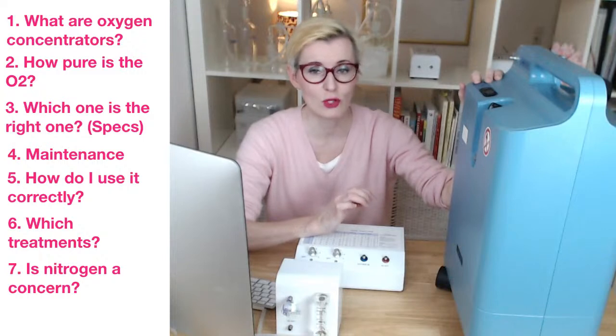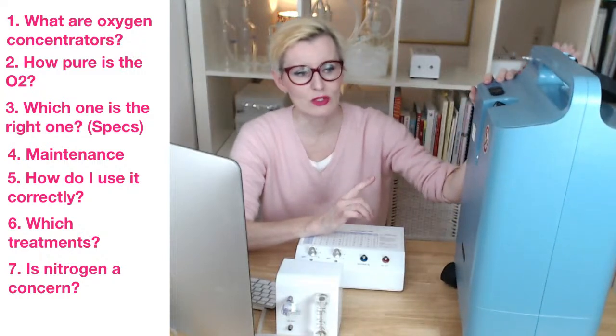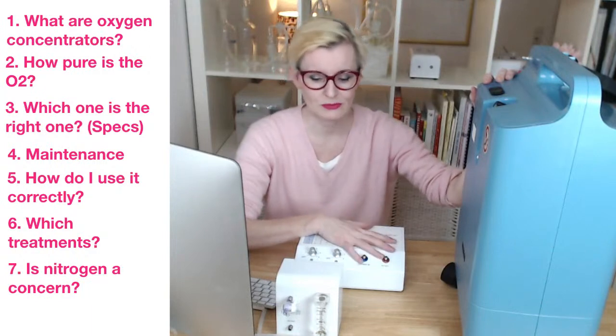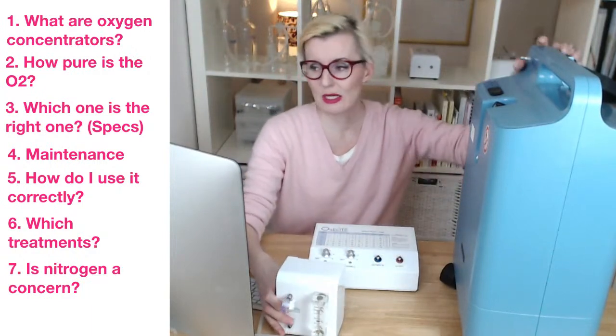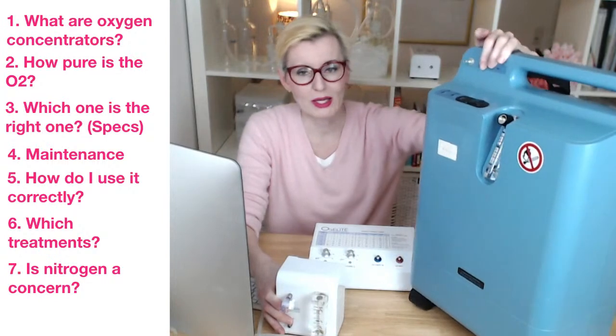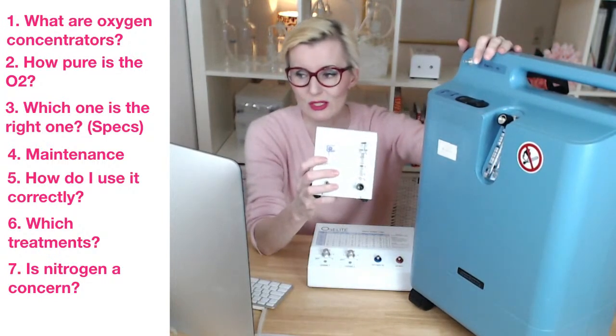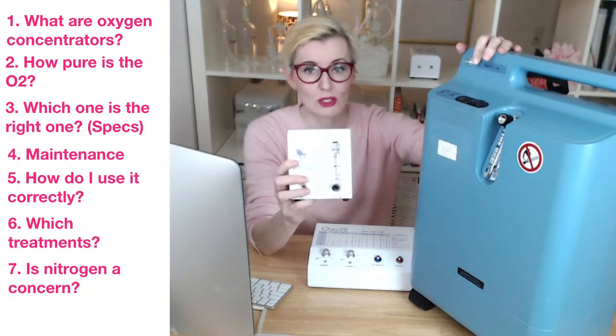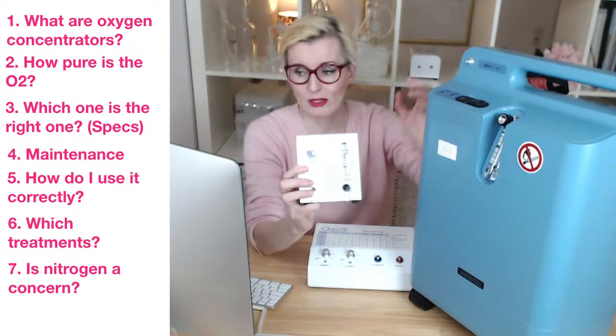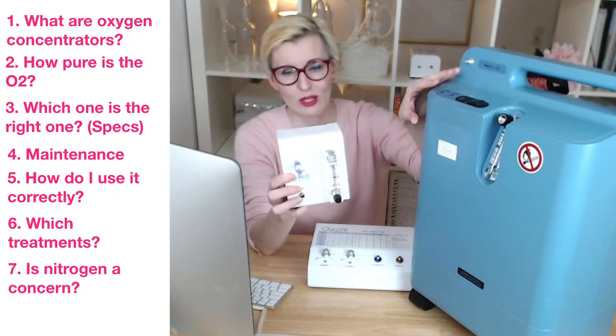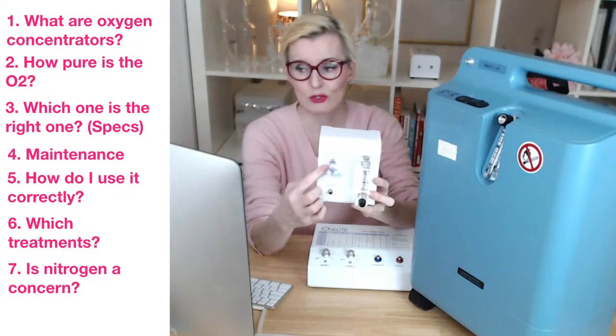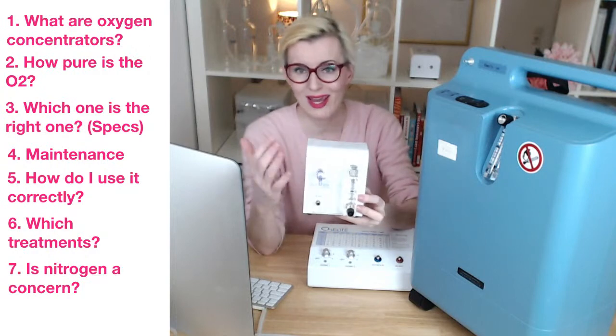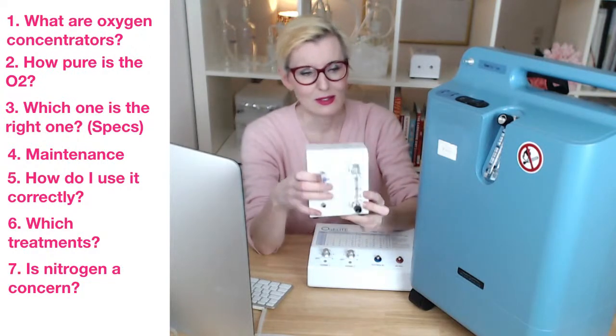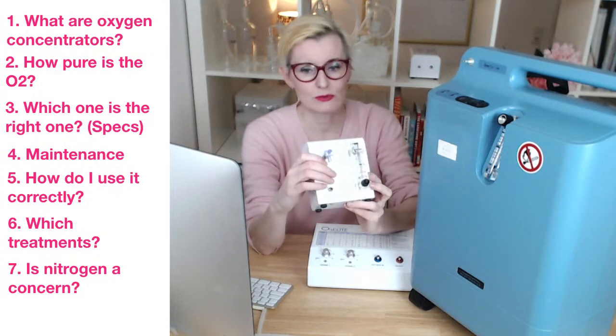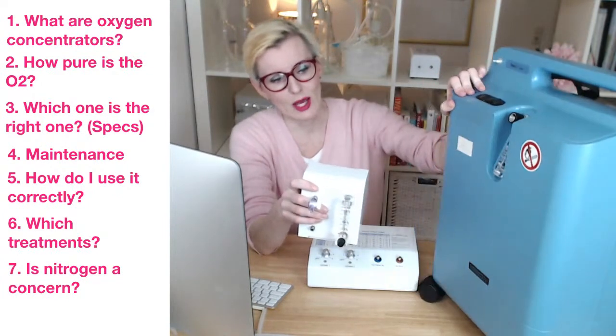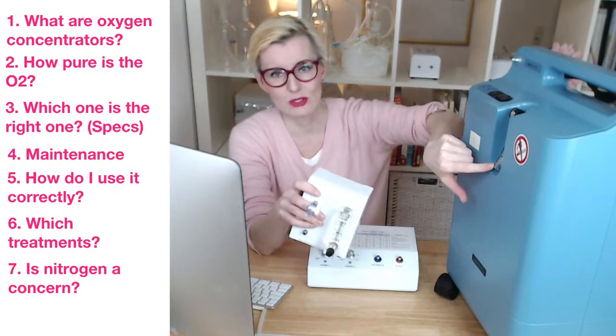90% oxygen at a flow of 2 liters per minute. Now this is important, that 2 liters per minute. The reason is that in most cases, if you buy an oxygen concentrator, you will also need something like this, which is an external regulator. The external regulator will turn the relatively high flow that the oxygen concentrator produces into low flows of like 1/8 of a liter per minute or 1/16. And in order to achieve this, the machine has to be set at 2 liters per minute.